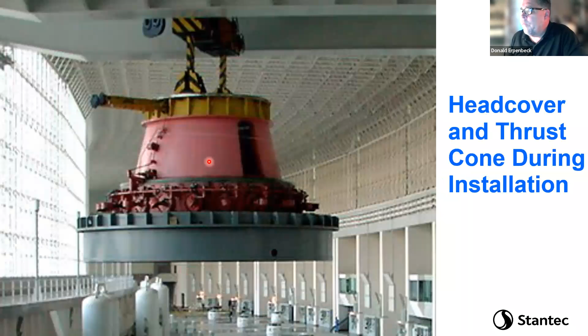Now, some facts about what was going on at the plant when it failed. Unit 2 had been refurbished earlier in the year, in April. About a month later, in May, it started to show an increasing rate of vibration in the machine. You see here this solid line is the limit where they should have stopped, where they tripped an alarm. It's a little under 200 micrometers peak to peak amplitude of vibration.